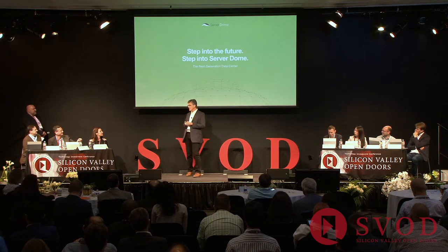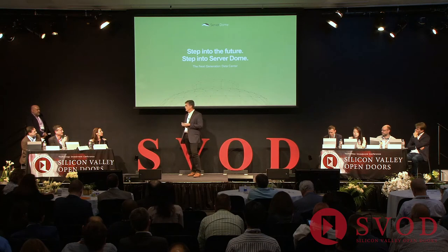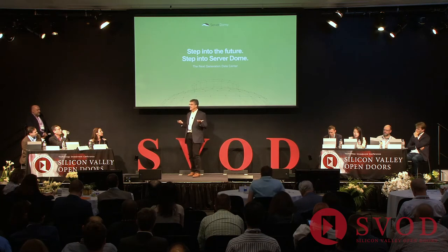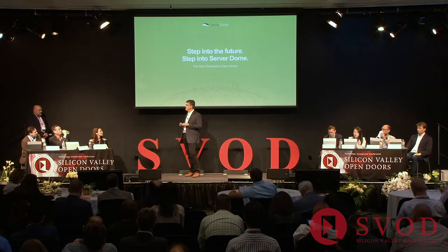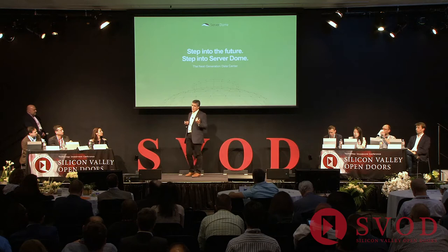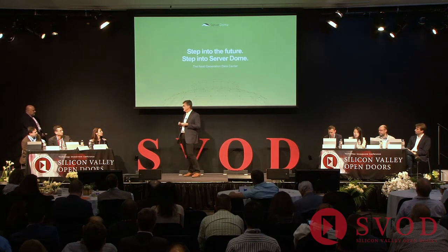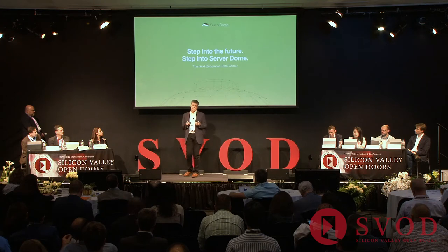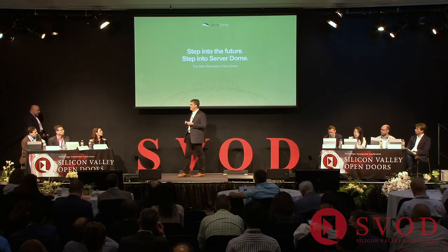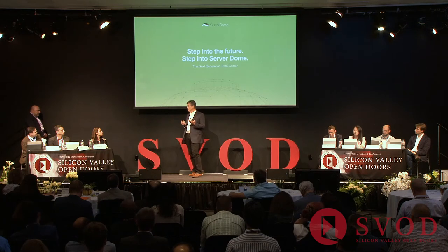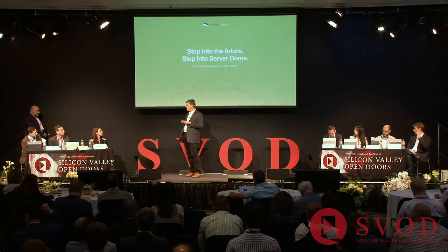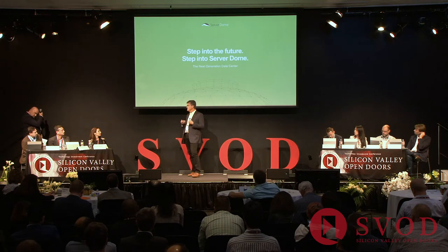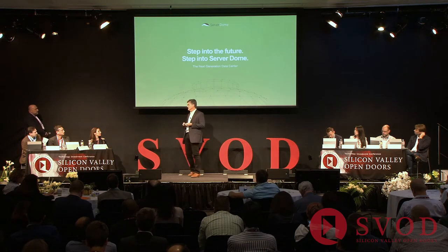As far as cost to build, we are very competitive because we have so many fewer mechanical systems. It's not an easy quantification because you have tiers of data centers and redundancy, so the cost per megawatt runs between $6 and $10 million a megawatt, which is clearly very justifiable. PUE on an average data center is 1.4. The newer data centers run 1.25 to 1.3. We've run for 3 years between 1.13 and 1.17, and in energy savings mode, 1.06. So in discussions with some of the innovative technologies coming out, we'll be able to get that even lower.